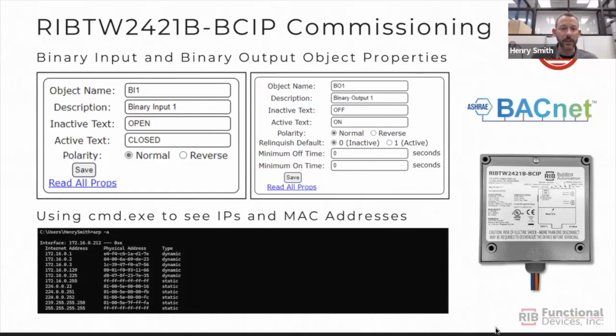These are the text fields that can be written to for those objects. For the binary input, you can reverse the polarity and define the text you want it to represent when the input's open or closed. Same way with the binary output, you can change the description, your inactive and active text, and then your minimum on or off time if you have some kind of setback.